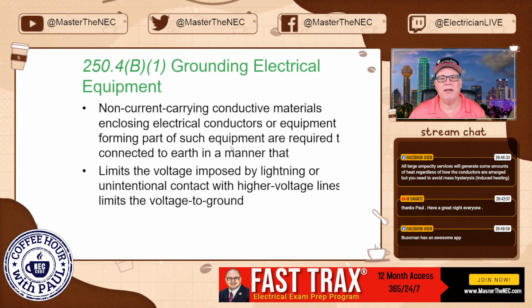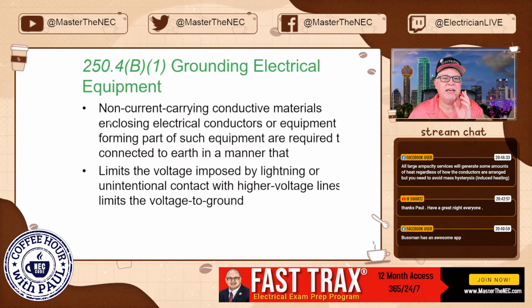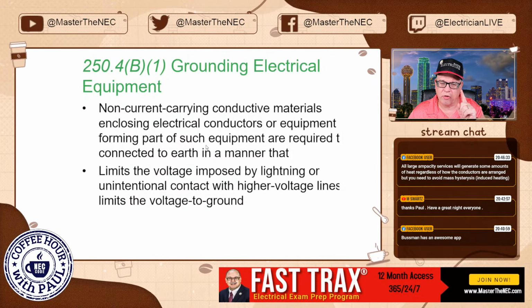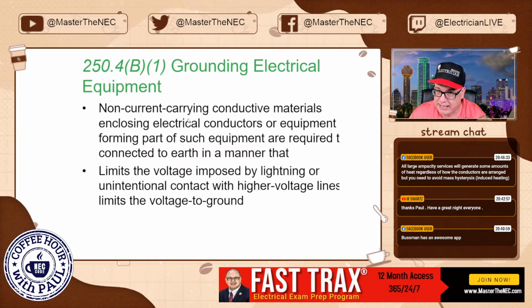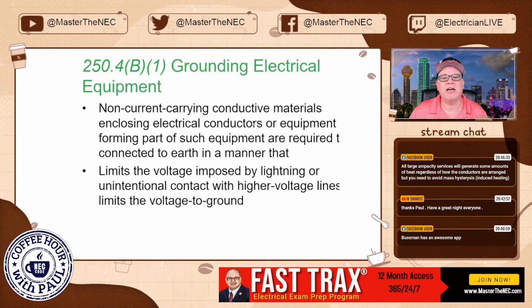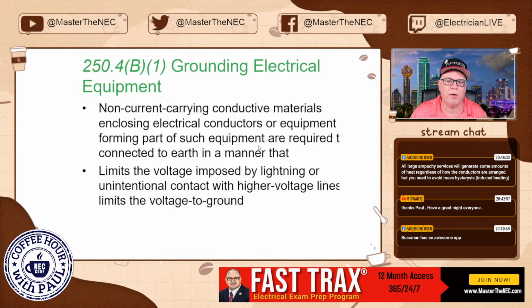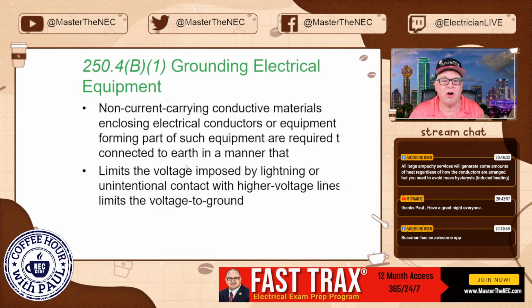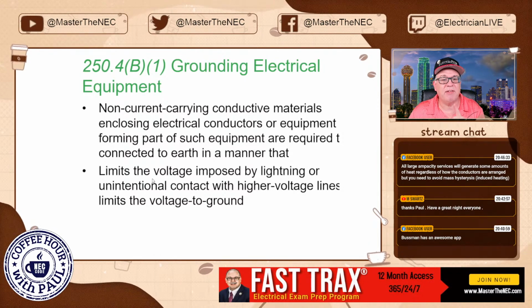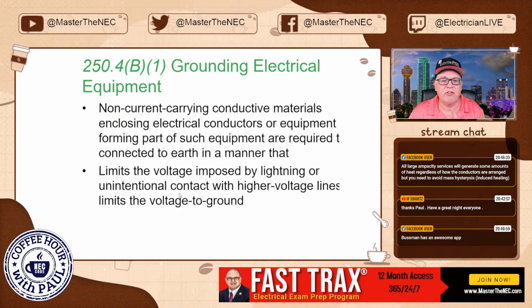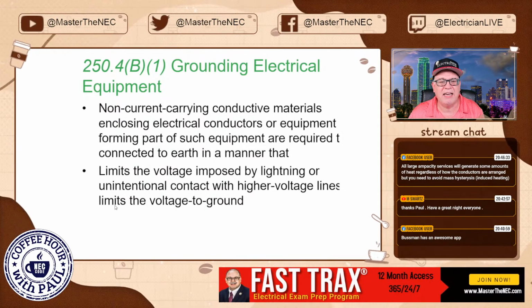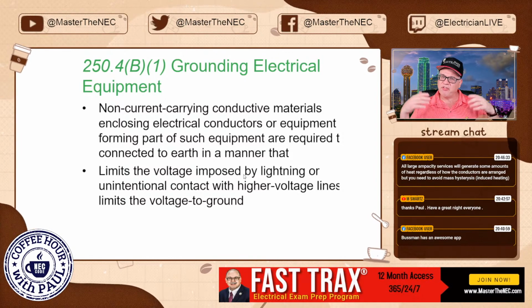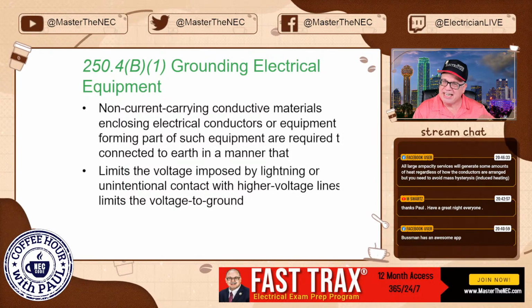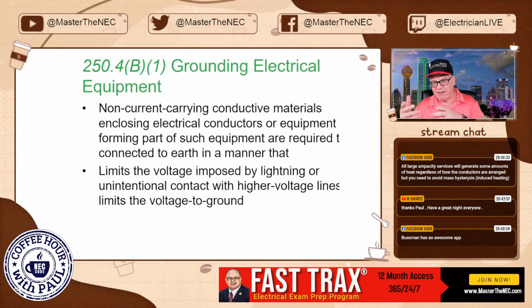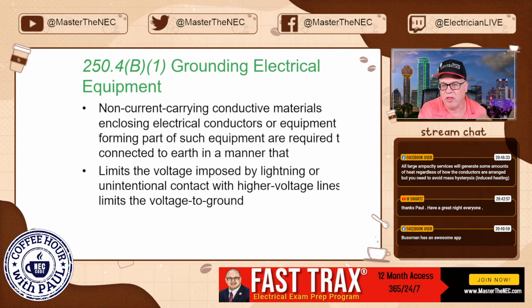All right, (B)(1), grounding electrical equipment. So let's talk about grounding electrical equipment. Remember, now we're talking about ungrounded systems here. So this would be the time for you to take a bathroom break if you don't really care about ungrounded systems. It says non-current carrying conductive metal enclosing electrical conductors or equipment or forming part of such equipment are required to be connected to earth in a manner that limits the voltage imposed by lightning or unintentional contact with high voltage lines and limits the voltage to ground. So we still have to take this equipment and connect it to earth. We're just not taking the system and taking a connection to earth, right?